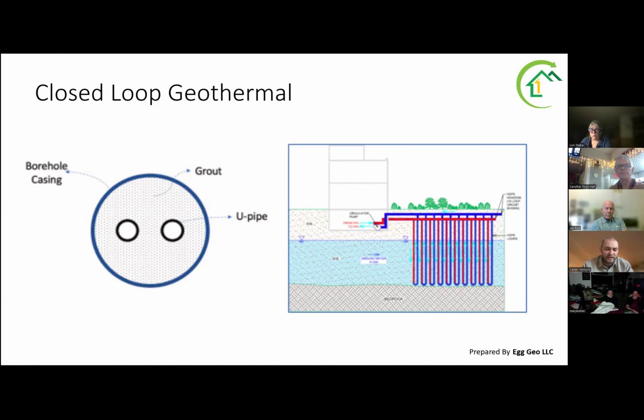Our analysis on this proved it was definitely a viable option. It's a great backup if we decide to do an open aquifer exchange system and end up finding we can't get the water we need. Our original analysis produced a result that said we would need 152 boreholes, assuming a depth of 500 feet, and an area of about 61,000 square feet, which gives us plenty of room with the drilling space we were given.